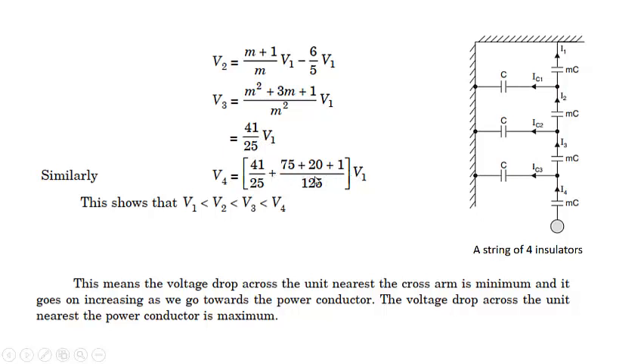So in that case, you will see that V4 will be greater than V3, greater than V2, greater than V1, which was the conclusion we have earlier made on the basis of the currents. So this means that the voltage drop across the unit nearest to the cross arm is minimum, and it goes on increasing as we go towards the power conductor. The voltage across this is less as compared to this, and this is less as compared to this. That means the voltage across the disk which is close to the power conductor will be highest, and the voltage across the disk which is close to the cross arm will be minimum.